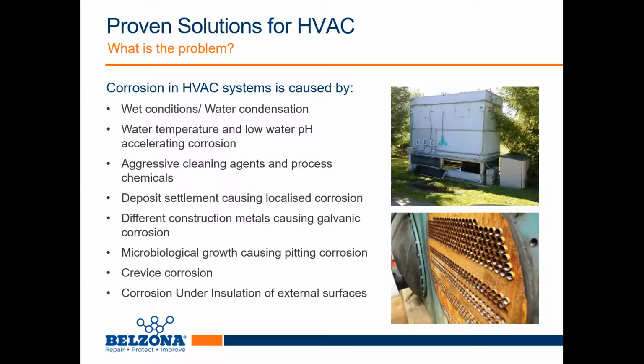Water pH: the pH in untreated water drops. Corrosion tends to increase. The lower pH also dissolves various oxides and exposes more of the metal surface to corrosion. Aggressive cleaning agents that are used to clean these types of systems, and the water treatment chemicals used to prevent scale and fouling, accelerate corrosion rates. They lead to perforations and holes and severe metal loss on units and surfaces. Deposits: low water velocity allows solids to settle and deposit on the metal surfaces. These deposits make it impossible for any corrosion fighting chemical to do its job. The protective film provided by the corrosion inhibitor settles on the deposit rather than on a metal surface. As a result, localized corrosion can thrive unchecked underneath these deposits.